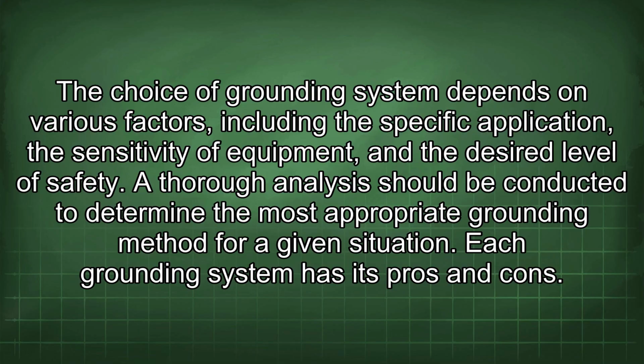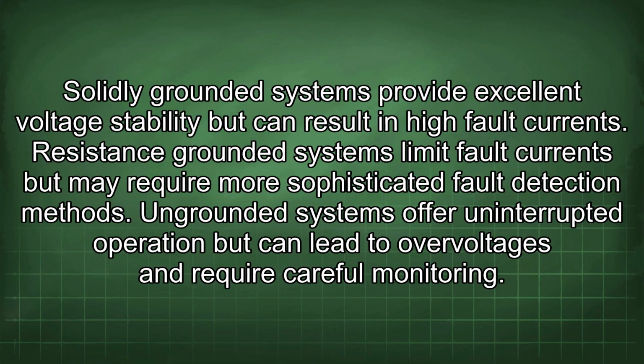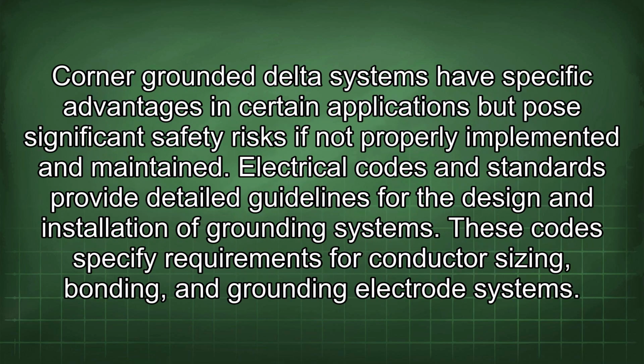Each grounding system has its pros and cons. Solidly grounded systems provide excellent voltage stability but can result in high fault currents. Resistance-grounded systems limit fault currents but may require more sophisticated fault detection methods. Ungrounded systems offer uninterrupted operation but can lead to overvoltages and require careful monitoring. Corner-grounded delta systems have specific advantages in certain applications but pose significant safety risks if not properly implemented and maintained.